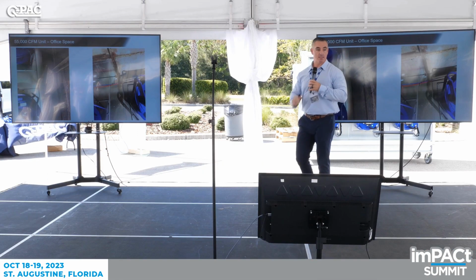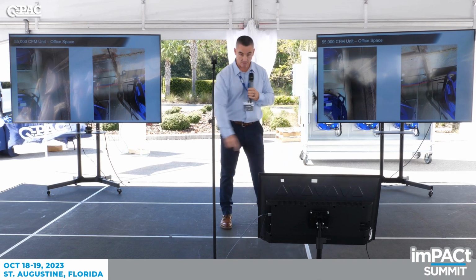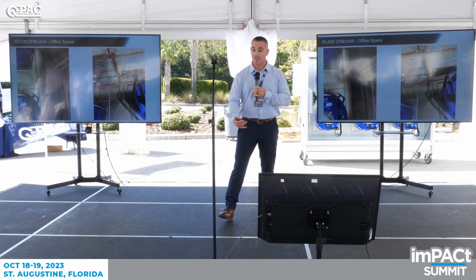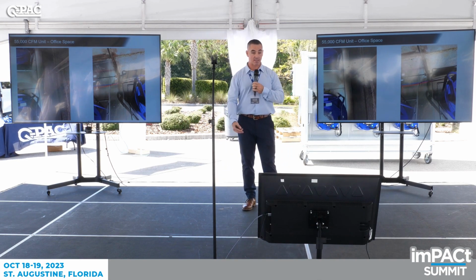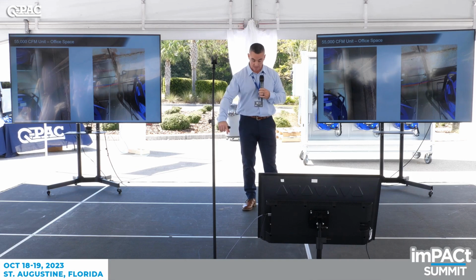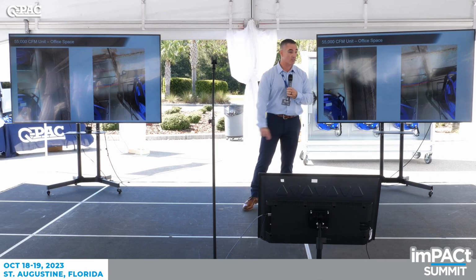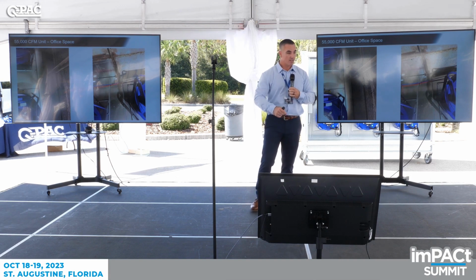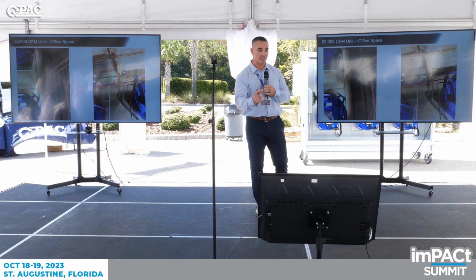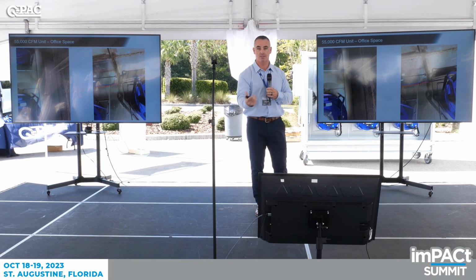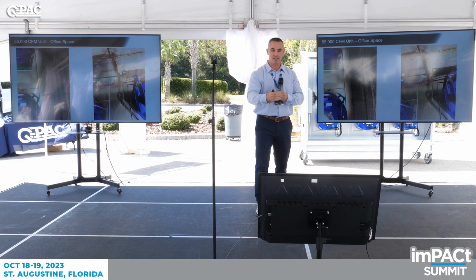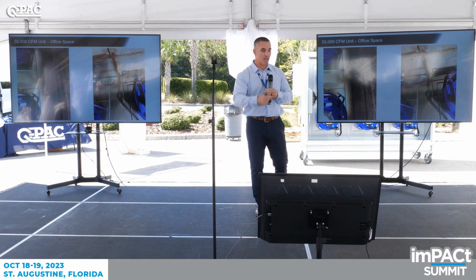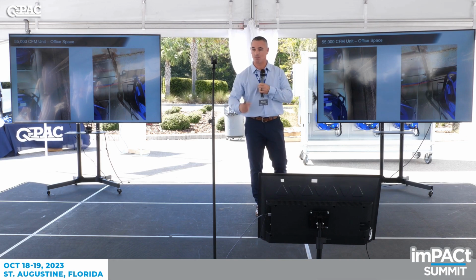So there are a lot of cases where you need to pay attention to what's on the floor. When you take the fan sled out, when they demo and take the fan sled out, sometimes old units have, along the edge of the outside of the unit, the floors down, and then it comes up an inch and over. You need to notch. The contractor needs to notch part of the bulkhead. It's easy to do, it's 14 gauge metal, but we need to work with Blake to make sure you have enough distance so they don't put one of their posts right there where you have to notch. You never want to notch where the post is, right?